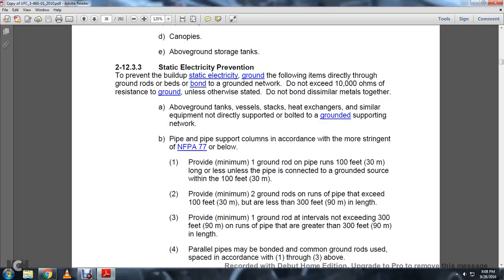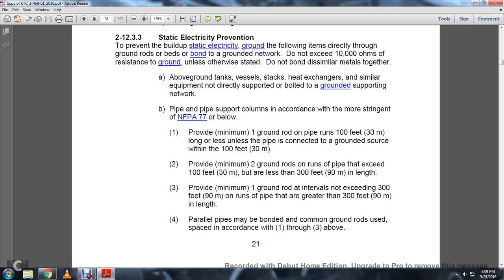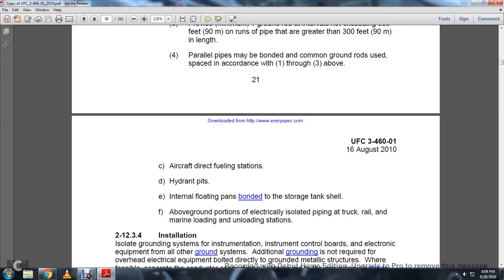Provide a minimum of two ground rods on runs of pipe that exceed 100 feet but are less than 300 feet in length. Provide a minimum of one ground rod at intervals not exceeding 300 feet on runs of pipe that are greater than 300 feet in length. Parallel pipes may be ground bonded, or common grounds may be used, spaced in accordance with 1 through 3 above. Also ground aircraft direct fueling stations, hydrant pits, internal floating pans bonded to the storage tank shells, and aboveground portions of electrically isolated piping at the truck and rail, marine loading and unloading stations.